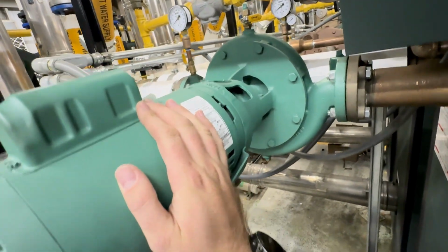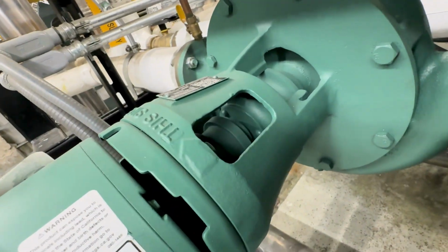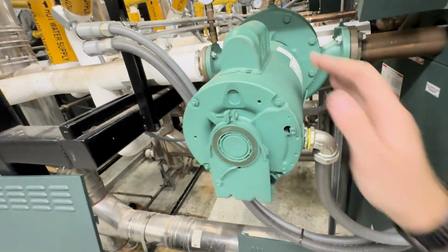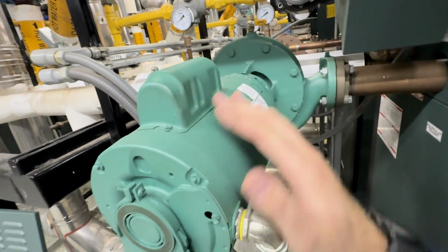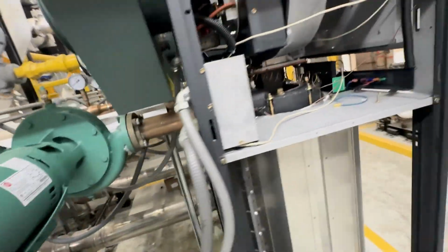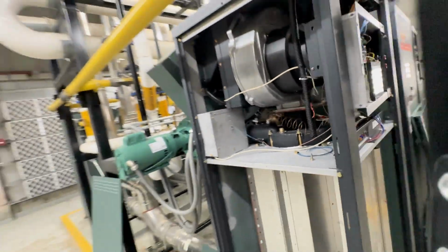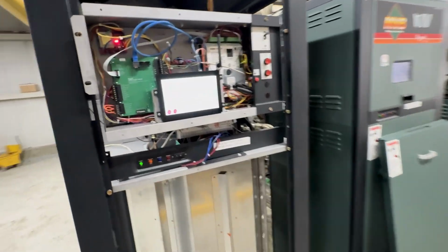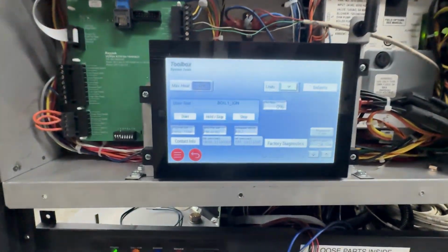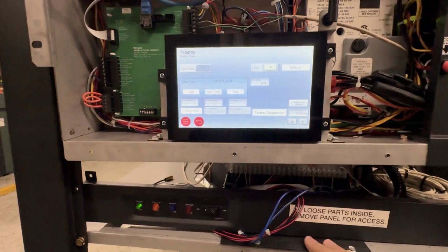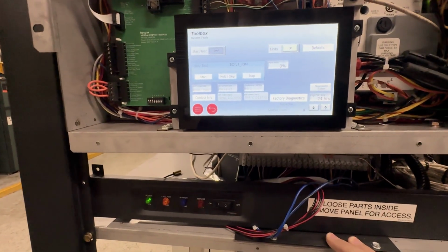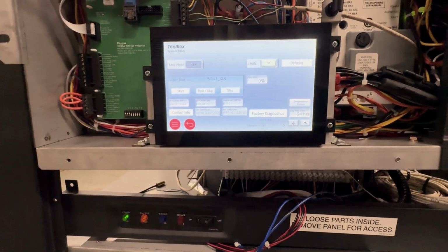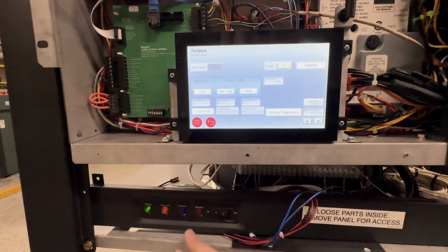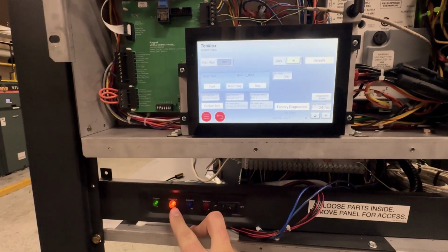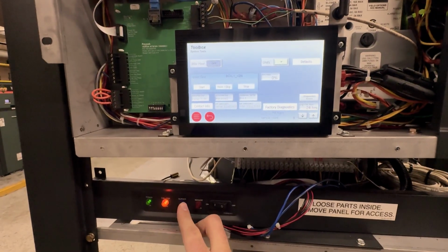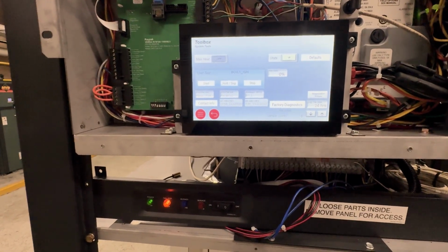Pump is on. Inspect the pump coupling. Motor sounds fine, doesn't sound like it has any bad bearings. The blower on the boiler just turned on. Should be trying to ignite. There's the call for heat. So we should hear the gas valve open shortly, and that blue light should turn on once the burner is ignited.